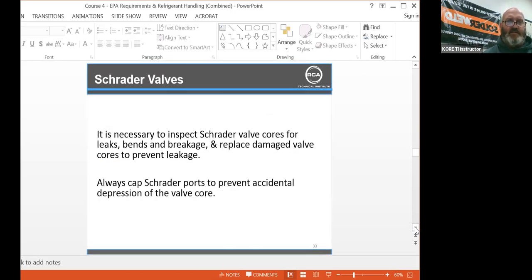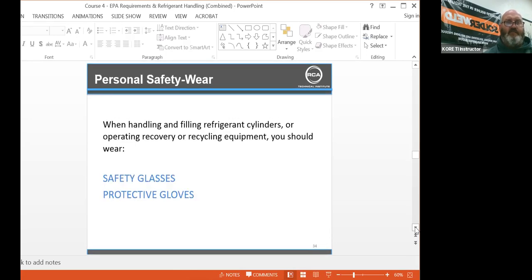It is necessary to inspect the Schrader valve cores for leaks, bends, or breakage. Replace damaged valve cores to prevent leakage. Always cap Schrader ports to prevent accidental depression of a valve core. You definitely don't want to drive down the road without those caps on. When handling and filling refrigerant cylinders or operating recovery or recycling equipment, you should wear your safety glasses and protective gloves. I've actually seen guys who had to go to the hospital with third-degree burns on their hands because the hose blows during recovery and they get a liquid refrigerant burn. It's horrible. It burns the skin just as bad as a flame.